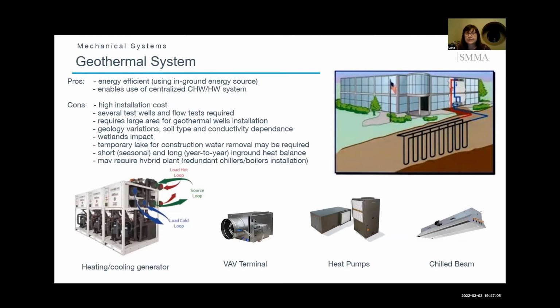Another factor is accounting for the space. Knowing that we have so many wells to drill, we need a large area to locate them. Usually they're planned on a 25-foot by 25-foot grid. This is the industry standard safe distance, so the heat exchange can happen freely within these wells. Also, the capacity of the wells depends on geology variations, soil type, and conductivity, so every well produces a slightly different result. That's why we drill more than one well.